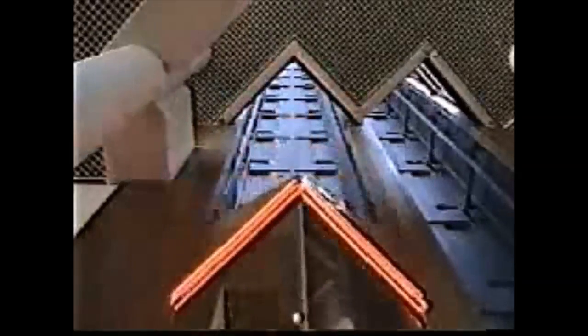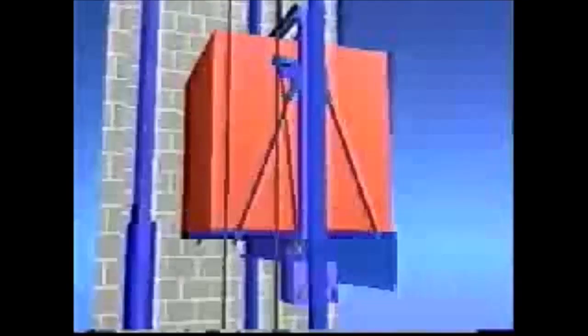The governor monitors the car speed, and in case of car overspeed the governor removes power from the elevator drive motor and sets the brake. If the car speed continues in the downward direction, the governor then sets up the safety. These are the types of safeties found only on a traction elevator.